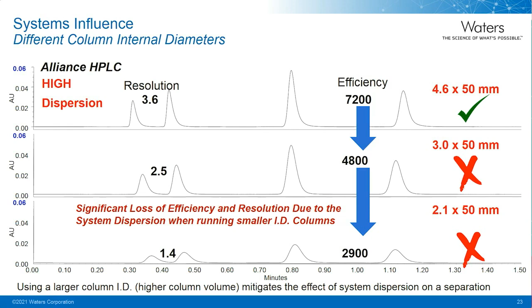Larger columns, typically 4.6 millimeter, perform best on this system because the ratio of the column volume to system volume is more favorable. The higher column volume is less impacted by the fixed system volume.